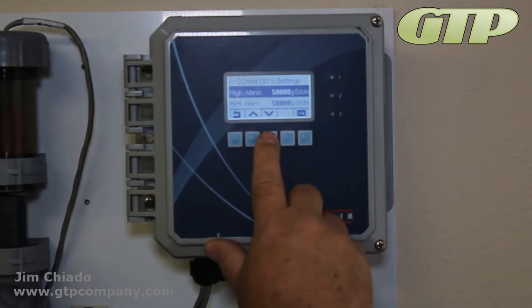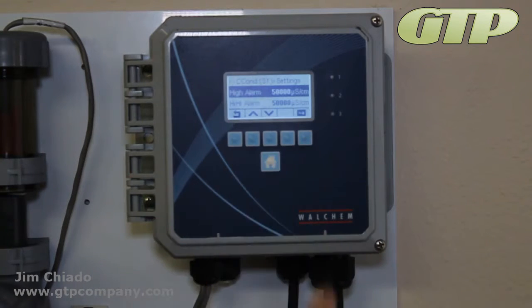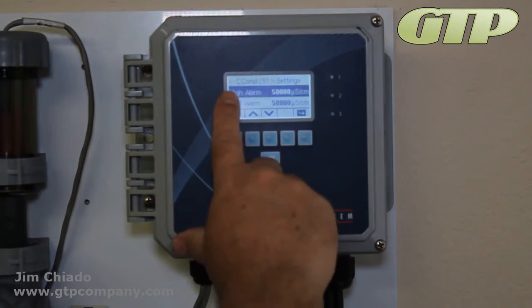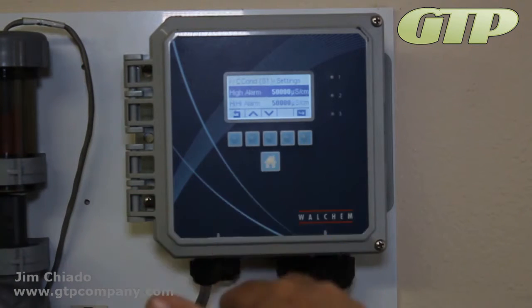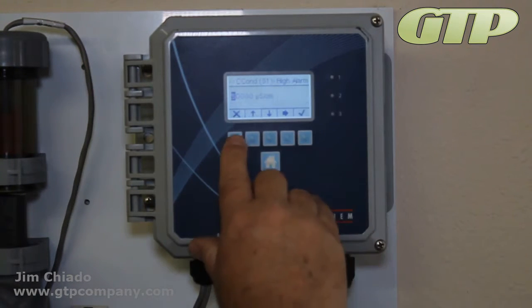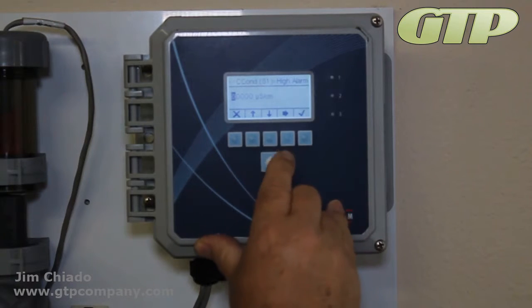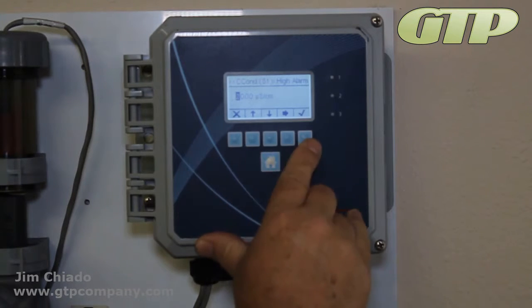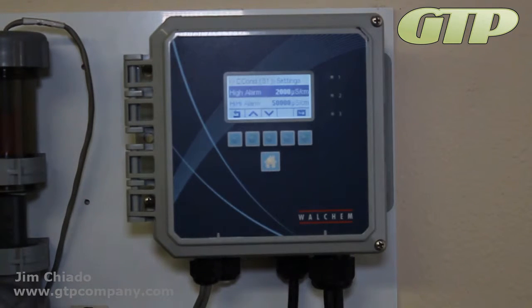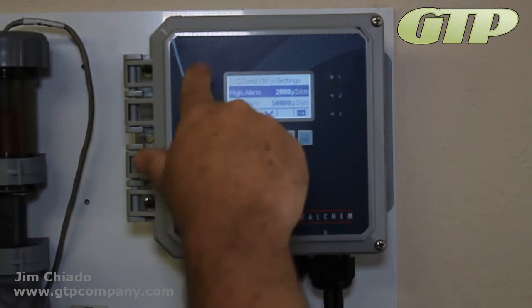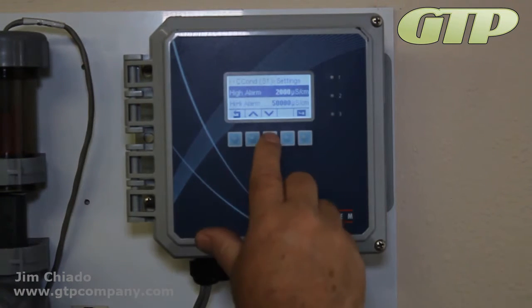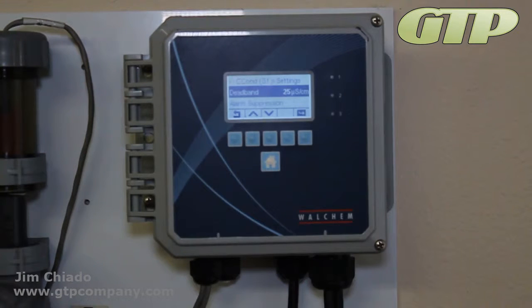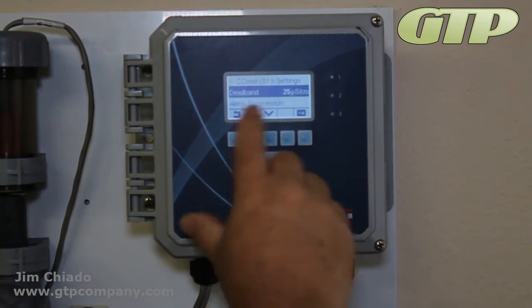Okay. Same thing with the high alarms. Right now they're set at 50,000 on the high alarm. If it's never bleeding, the bleed valve is stuck closed or it's clogged. The high alarm really should be, if you're operating at 1500, we'll say we'll make this 2000. So we're going to go in here, down arrow key this, at least to 0. You can actually go past it. We're going to go 2000. So now, if it ever gets that high, the alarm will go off. It'll say high alarm. At least everybody's notified. It is a nice feature to have, so if somebody ever just walks by, they'll see it at least.